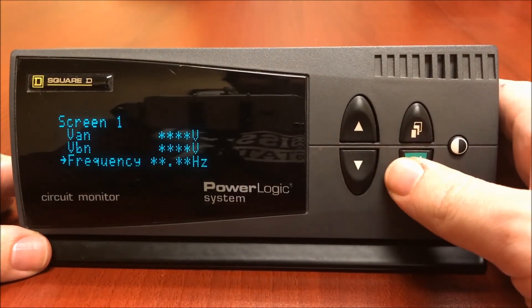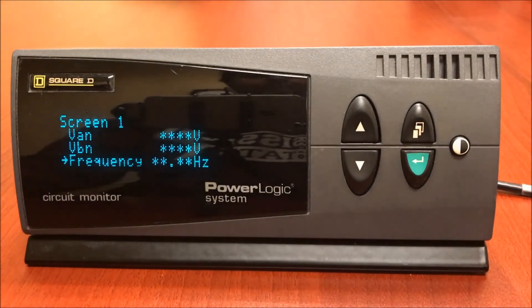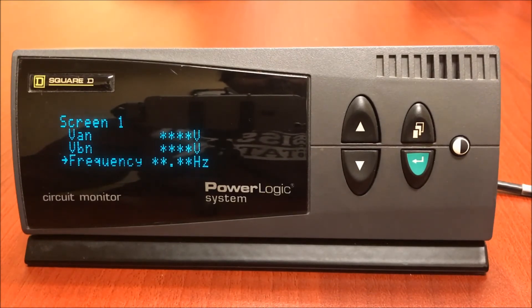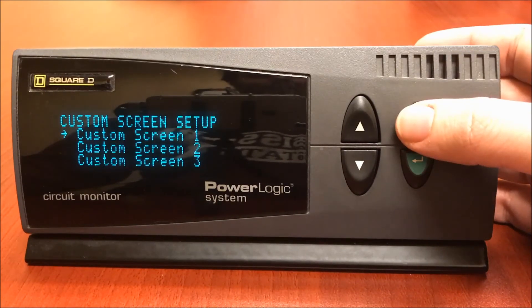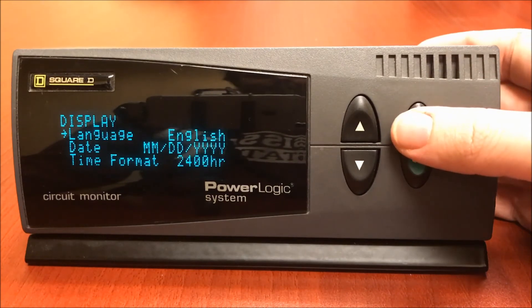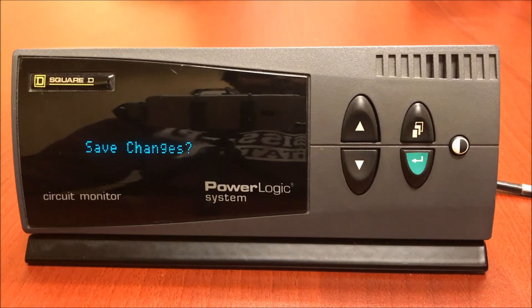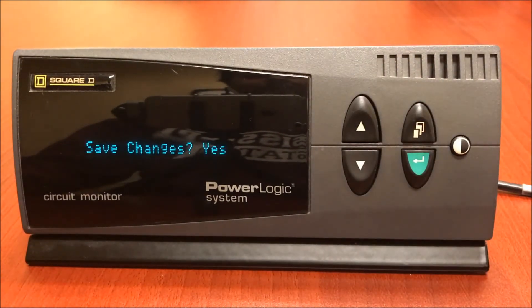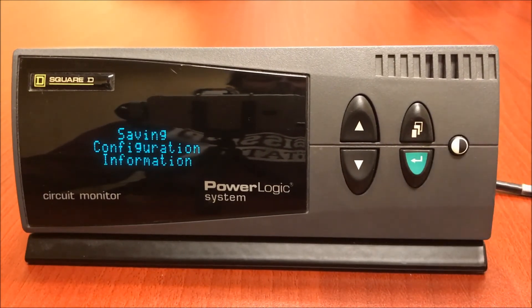Let's try frequency this time. Now that I have my three measurements added under the first custom screen, to save these settings I'm going to hit the menu button several times. It will ask us to save changes. We want to hit the up arrow to select yes. To finalize, hit the enter button. The meter will now do a quick reboot.